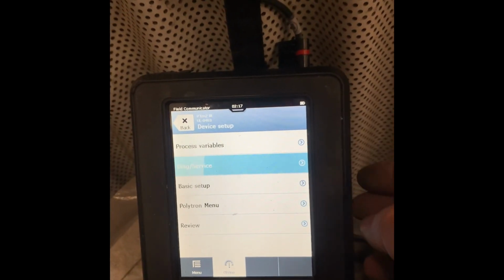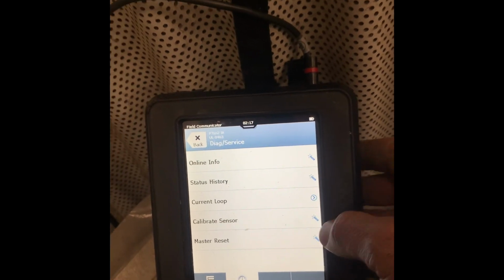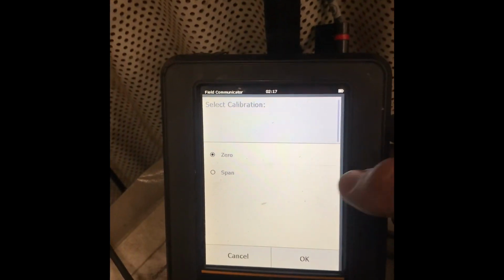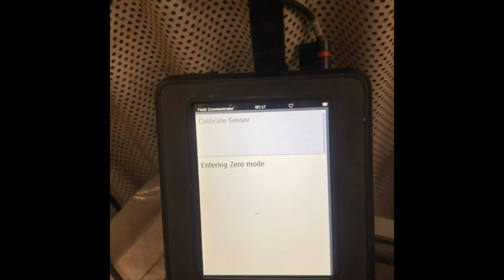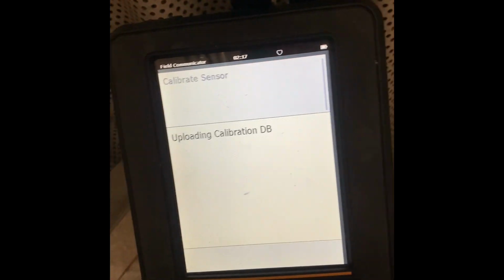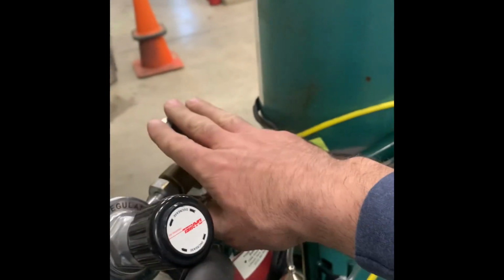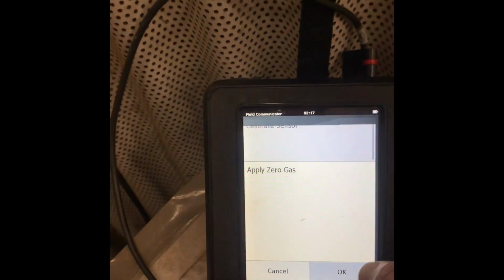in the previous screen I had 0 for an output, or 4 milliamps for an output. I'm just going into my calibration menu here, and this shuts off the alarms once you're in the menu. So right now I'm zeroing it out, and I have nitrogen flowing through it. So here's the tube coming from my nitrogen bottle. I have a low flow valve at the end of that.